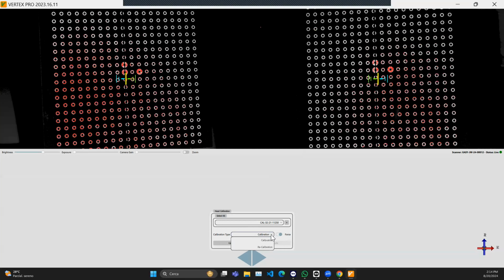We can choose between calibration and recalibration. Recalibration takes less time, but we define fewer parameters, not modifying the optical parameters. Force means that we run a calibration, then the software compares it with the last one done and decides which one has to remain. The suggestion is to always use calibration and always force, so we always go ahead with the latest calibration. Okay, and then we do calibration.